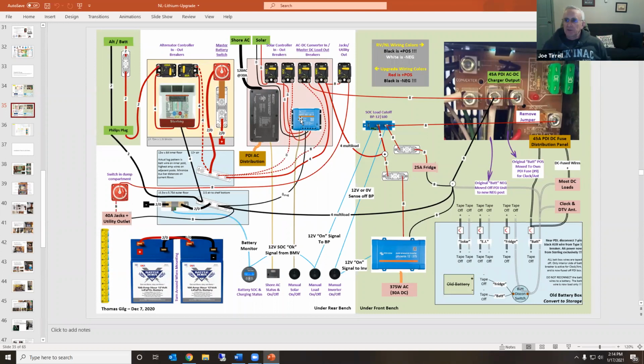So your circuit breaker, as long as it's rated less than your wire, you should be okay. But if that's not the case—if the charge controller shorts and your circuit breaker won't do anything—then yeah, I can see what you're saying could affect it. So it'd be good to get that information. Yeah, I'll look for that.